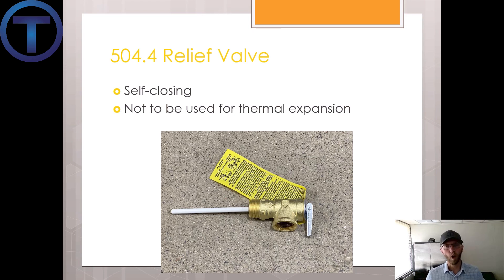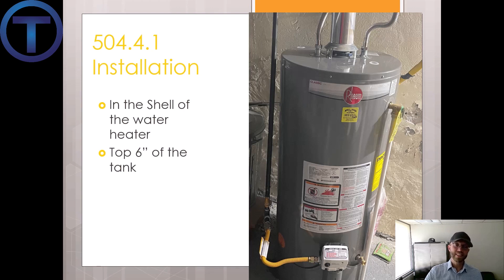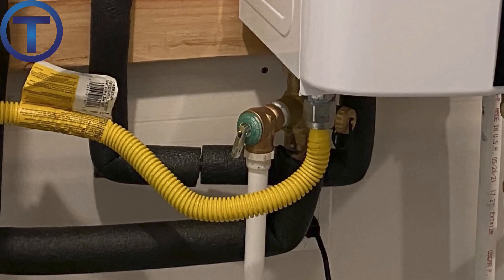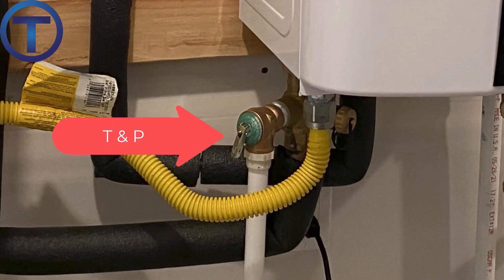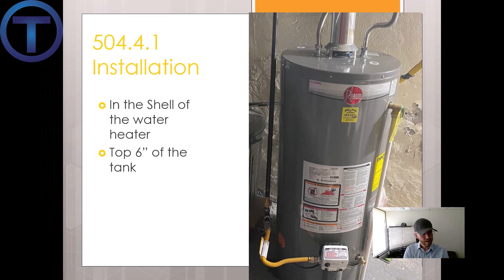That's not what the temperature pressure relief valve is for. It should be in the shell of the water heater and within the top six inches of the tank. On tankless water heaters this is a little different since there isn't a tank — there is a temperature pressure relief valve but it's not on the tank itself. On a tank-type unit, it is in the shell towards the top six inches, and can be on the side or come out the top.